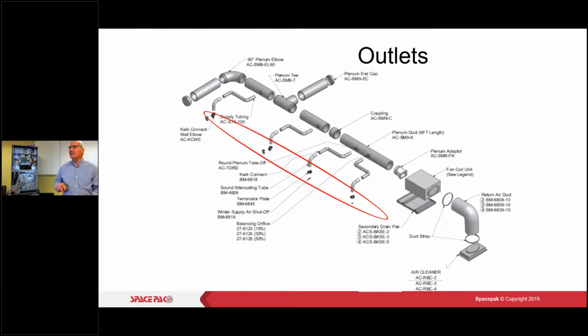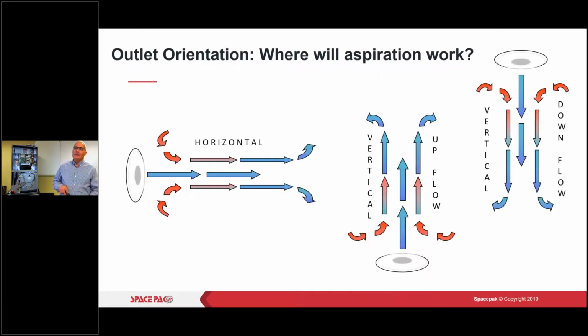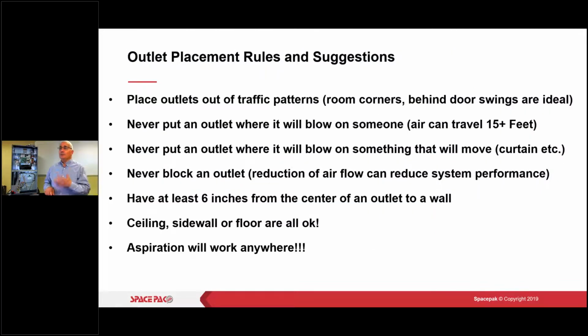So now we're going to get into our outlets. Again, we can orient them in all these different fashions, horizontal, vertical, all right, from the floor and or the ceiling. Placement's important. Put them in an area where that column of air is not going to disturb anybody. All right, so corner of the rooms behind door swings are really ideal. Never put it where it's going to blow on somebody because the air can travel 15 plus feet. So again, if Mr. Smith sits in that corner in his Lazy Boy and you've got it blowing right on top of him, not a good idea, all right?